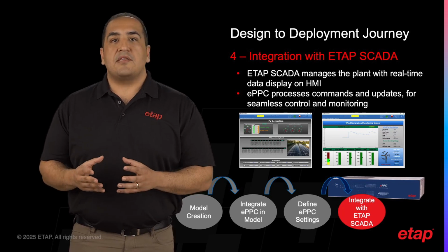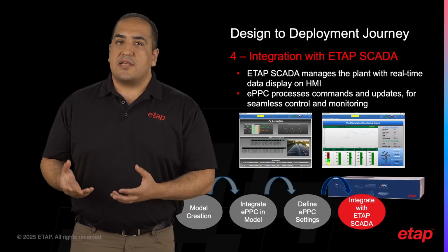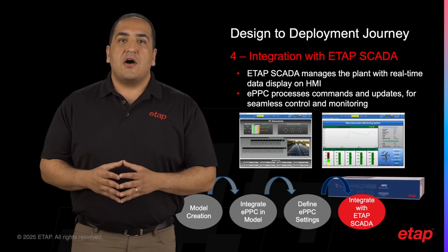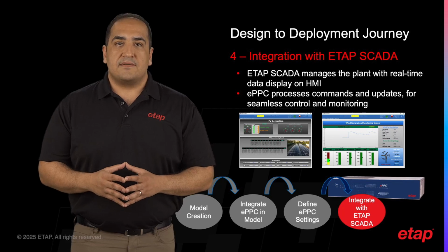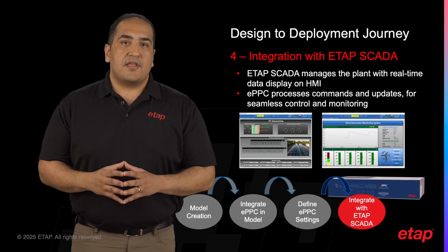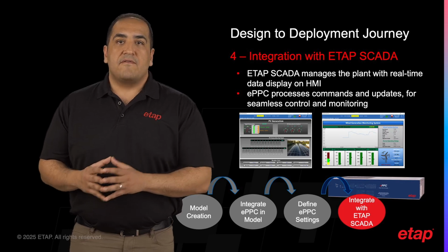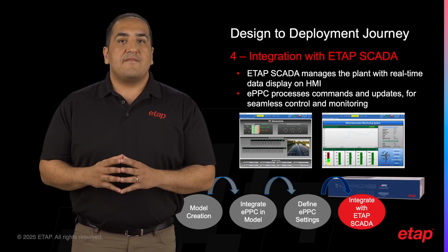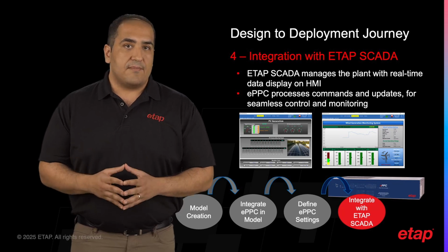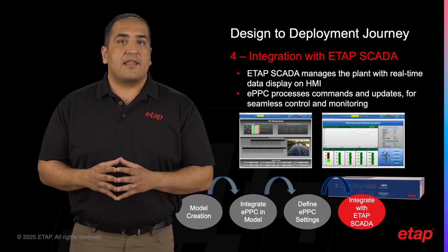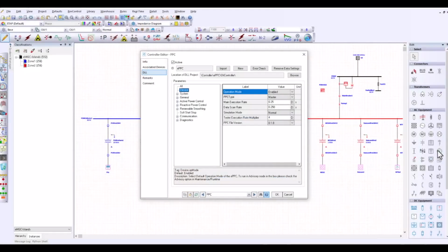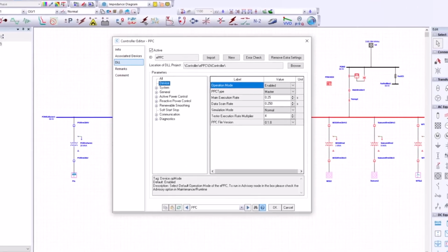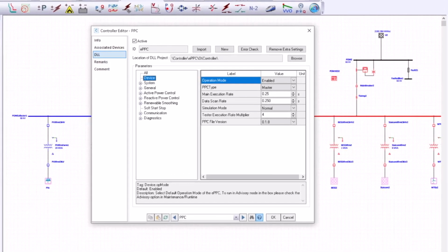Simultaneously, the HMI displays the updated information, raises any alarms or notifications, and logs all transactions and data for future analysis. This integrated, model driven approach ensures that every step from design to operation is handled within a unified and highly reliable environment, reducing the potential for error and enhancing overall efficiency. The final step in our process is hardware in the loop or HIL testing, SCADA integration, and deployment. This step ensures that the control logic we developed in ETAP functions correctly when interacting with real-world systems.